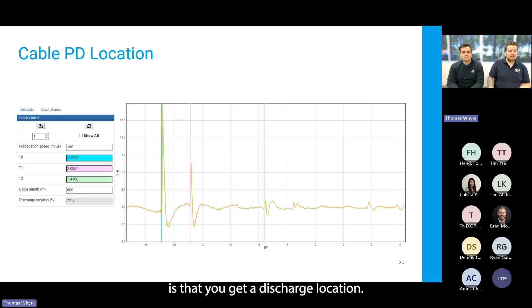And the really important thing to note is it's not necessarily new information nor groundbreaking, but it's the first time that we've actually been able to implement this onto the Plus². So previously, before we did a lot of the optimization, we only used to capture 50 waveforms, which you could look at and do this manually, but there wasn't often enough data to do it. If you wanted to do that really in-depth cable testing, you used one of our other products called the cable data collector. However, as we've put a lot of work into this and we're capturing more data at a quicker rate, nowadays you're actually capturing up to 500 waveforms per test. So you can go through those individually, you can do this full testing and functionality and location, all with the Plus² that you've been using all along.